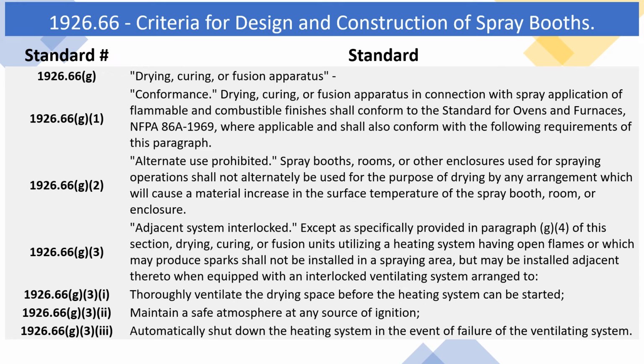1926.66 G2 Alternate use prohibited. Spray booths, rooms, or other enclosures used for spraying operations shall not alternately be used for the purpose of drying by any arrangement which will cause a material increase in the surface temperature of the spray booth, room, or enclosure. 1926.66 G3 Adjacent system interlocked. Except as specifically provided in paragraph G4 of this section, drying, curing, or fusion units utilizing a heating system having open flames or which may produce sparks shall not be installed in a spraying area, but may be installed adjacent thereto when equipped with an interlocked ventilating system arranged to: G3-1 Thoroughly ventilate the drying space before the heating system can be started. G3-2 Maintain a safe atmosphere at any source of ignition. G3-3 Automatically shut down the heating system in the event of failure of the ventilating system.